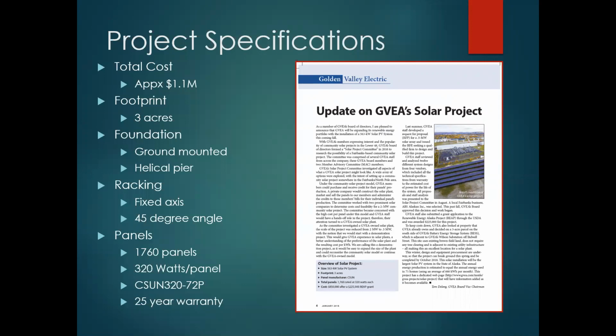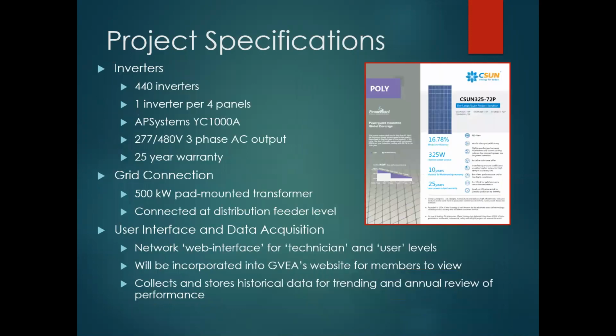That'll roll into some qualifiers here. More specifications: there are 440 microinverters, so the plant or farm outputs 440 kW AC. The collection is all done at the AC voltage level, 3-phase 480 volt. The inverter is also warranted at 25 years, and the grid connection will be done through a distribution feeder we have immediately adjacent, through a 500 kW pad mount transformer.